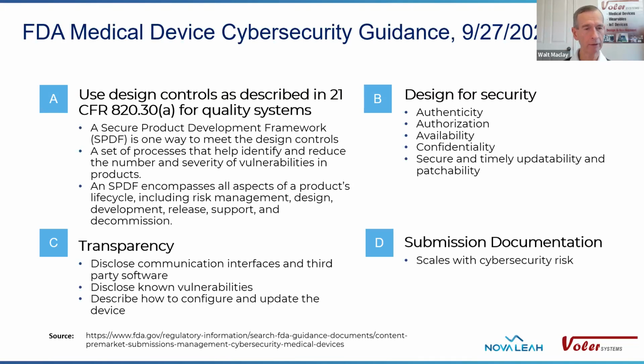Transparency is important. As was mentioned, the communication interfaces of your device need to be described. The third-party software described in the SBOM. You need to disclose the known vulnerabilities, and you need to describe how to update the device and how to configure the device, and not just the device, but the whole system. The documentation that's needed, well, all that we're talking about here is going to be documentation, but the FDA realizes that it scales with the risk. So a very risky cyber secured device will need more documentation. Next slide.